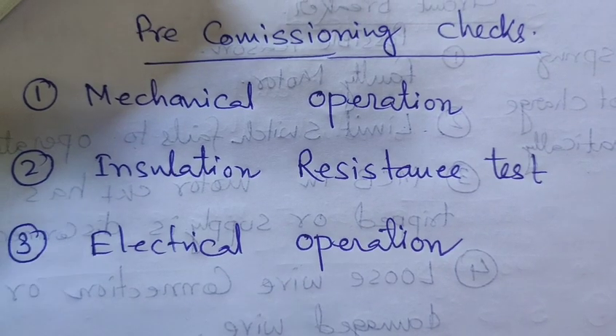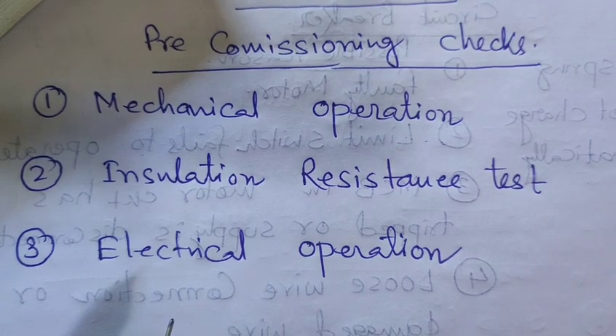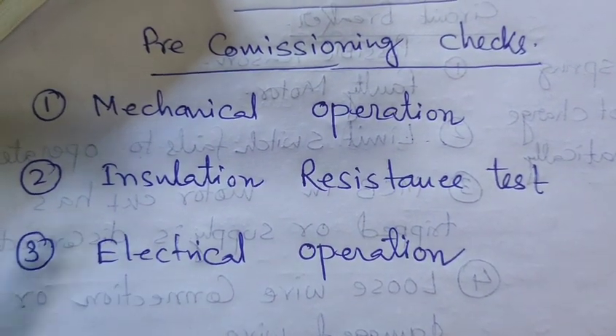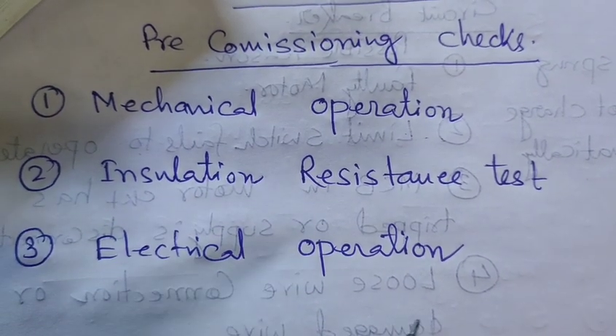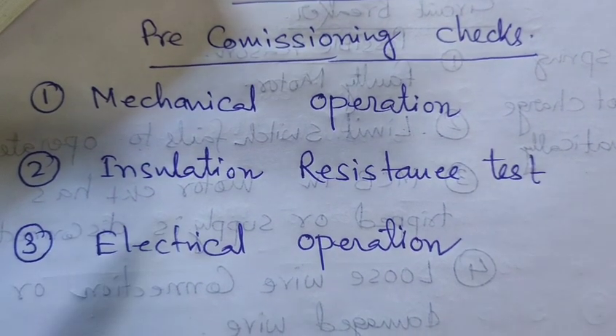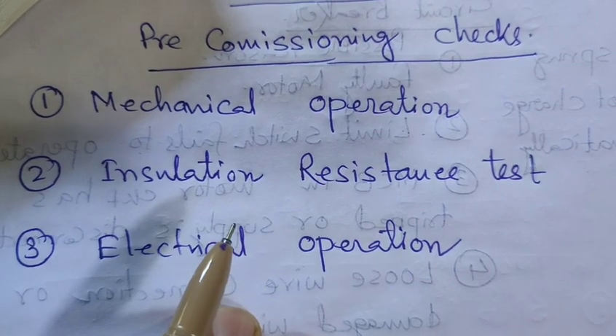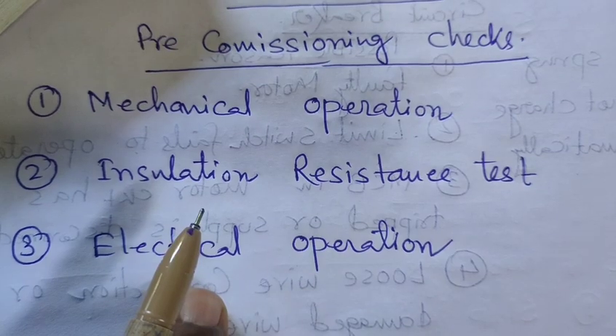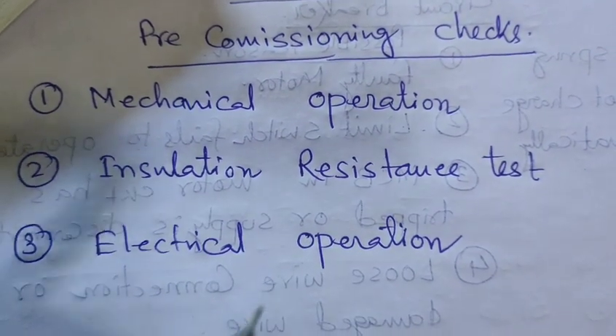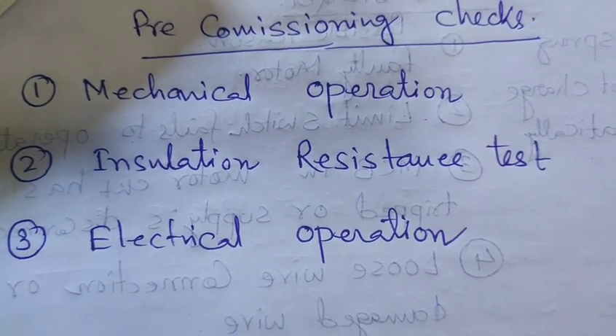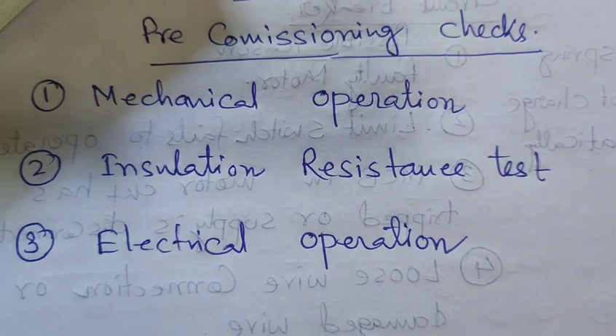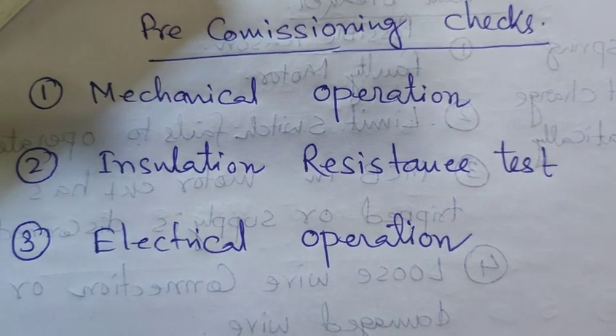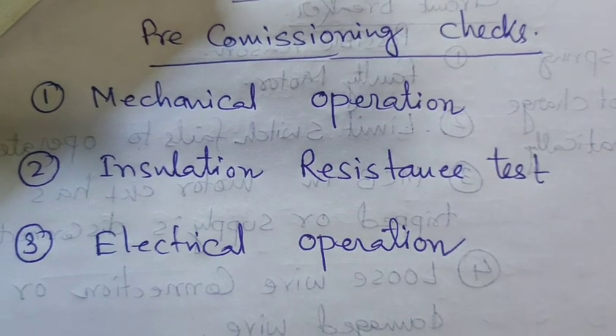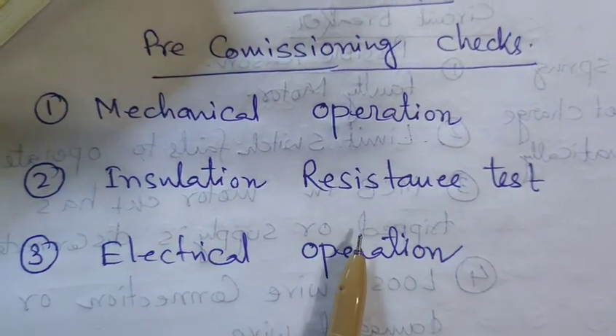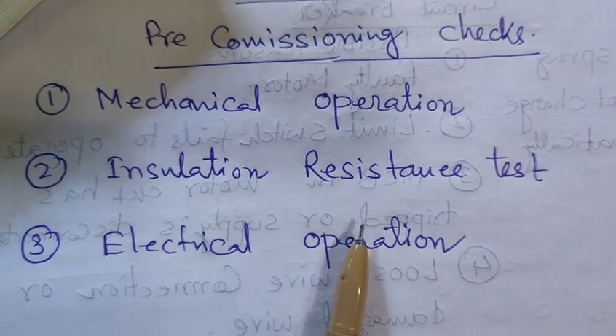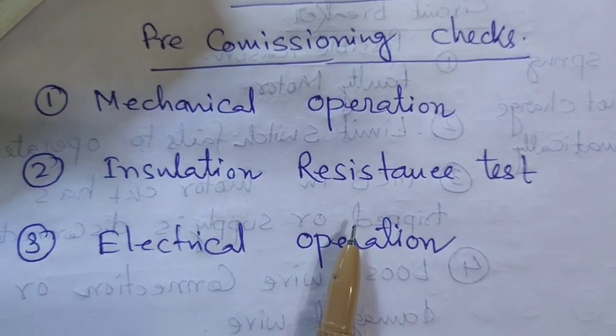When the spring charging has been completed, the breaker is ready for the mechanical operation, switching on and switching off. When the spring charge is completed, a mechanical indication will show that the spring is charged. First press the green button, for any internal spring charge positioning error correction. All the latches will then be placed properly. Then push the red mechanical push button for the mechanical operation of the circuit breaker. After pushing the red switch, the circuit breaker will operate. That means if the status was off before, now the status will be on. So this is the mechanical operation.